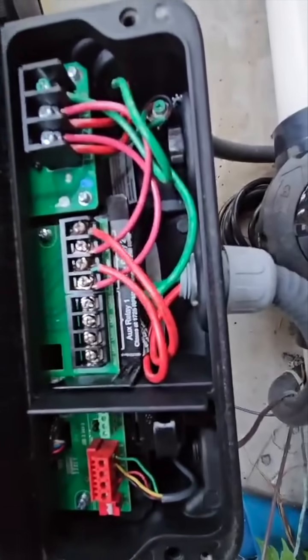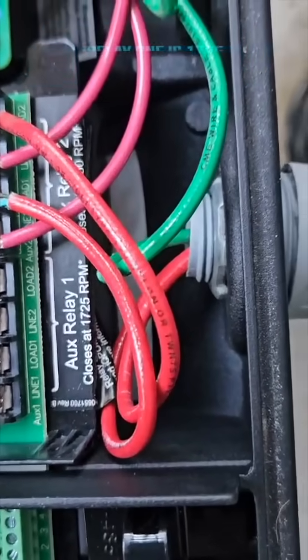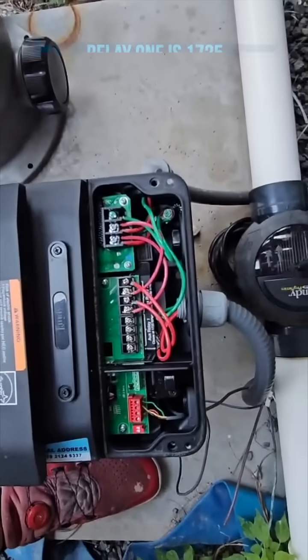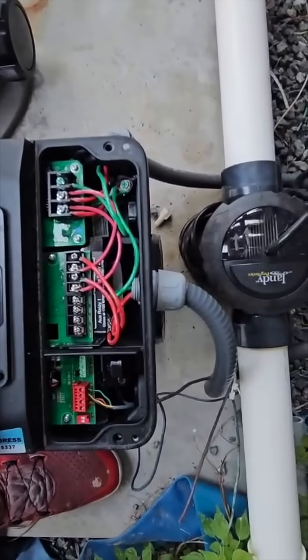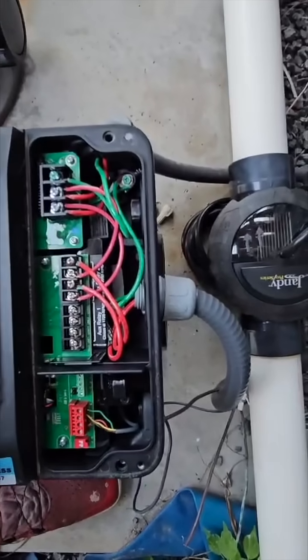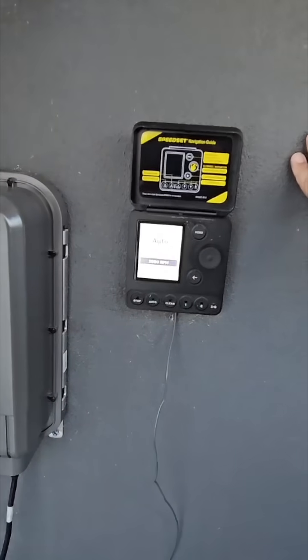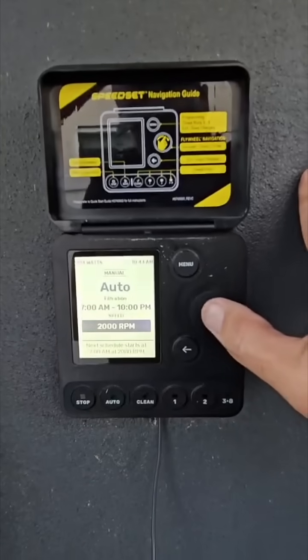Relay one is not hooked up, but you can see the numbers here — 1750 right there, 2250 right there. What that means is the pump has to be going at least that speed before it will open, basically turn on and pass power. Up here at the speed set, we are at 2000 RPM.